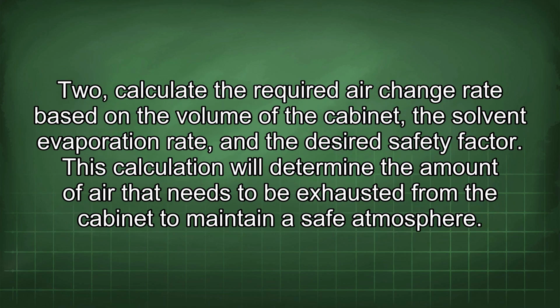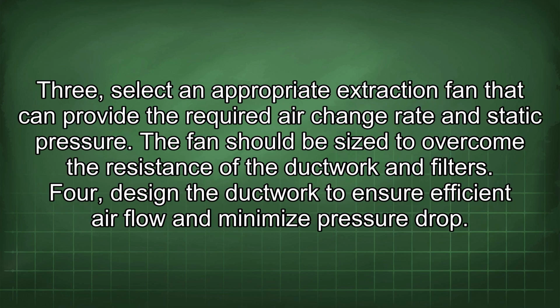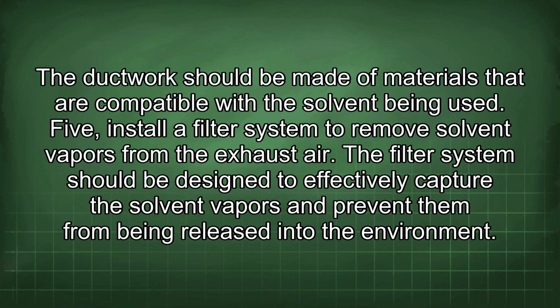2. Calculate the required air change rate based on the volume of the cabinet, the solvent evaporation rate, and the desired safety factor. This calculation will determine the amount of air that needs to be exhausted from the cabinet to maintain a safe atmosphere. 3. Select an appropriate extraction fan that can provide the required air change rate and static pressure. The fan should be sized to overcome the resistance of the ductwork and filters. 4. Design the ductwork to ensure efficient airflow and minimize pressure drop. The ductwork should be made of materials that are compatible with the solvent being used.